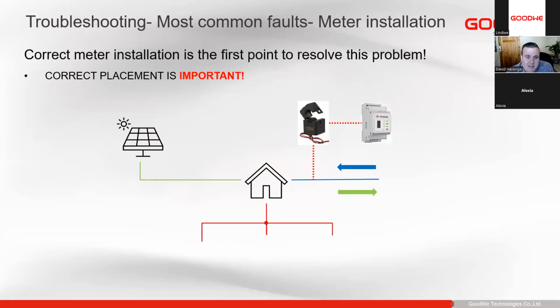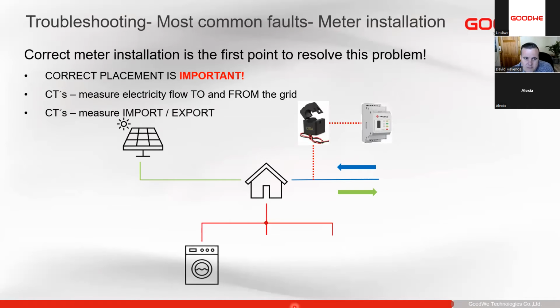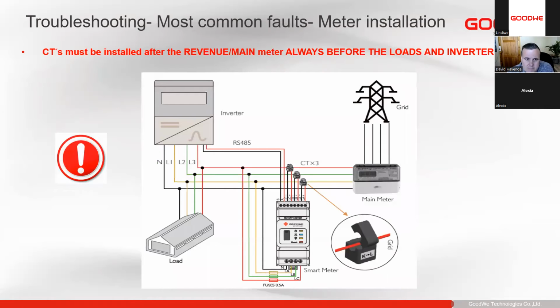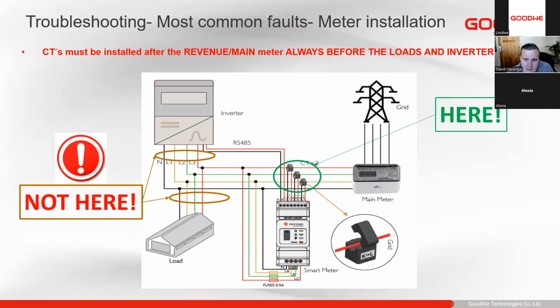So meter placement is very, very important. So the meter needs to measure the flow to and from the grid. So it's very important that we put our CTs on the correct place. So we never install the CTs under the inverter, never install the CTs between the inverter and the loads. We must make sure to always install the CTs between the utility and the entire property. So it must be able to read the loads as well as the inverter's production. So as close as possible to the utility meter is always recommended, or the main input cables from the utility into the home or building.